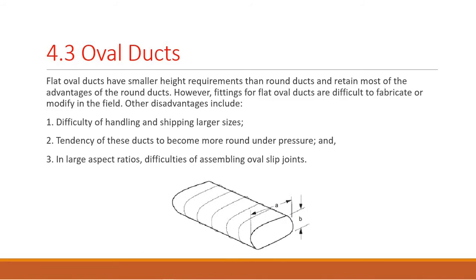Oval ducts. Flat oval ducts have smaller height requirements than round ducts and retain most of the advantages of round ducts. However, fittings for flat oval ducts are difficult to fabricate or modify in the field. Other disadvantages include: difficulty of handling and shipping larger sizes, tendency of these ducts to become more round under pressure, and in large aspect ratios, difficulties of assembling oval slip joints.